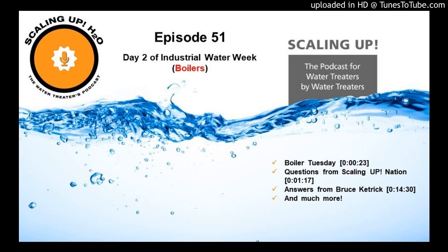You could be looking at the situation where it would be difficult in one of those boiler systems, especially with high condensate return, to be able to even get to 1,200 micromhos conductivity in the boiler. So the limiting factor becomes the fact that you still have to have some blowdown. You are still feeding some dispersant, but it really is on a case-by-case basis. And you're going to have to make sure you have somewhere in the neighborhood of 0.2 to 0.5% blowdown, just to make sure you've removed some of the solids that accumulate in the system. Other than that, it's balancing the chemistry.